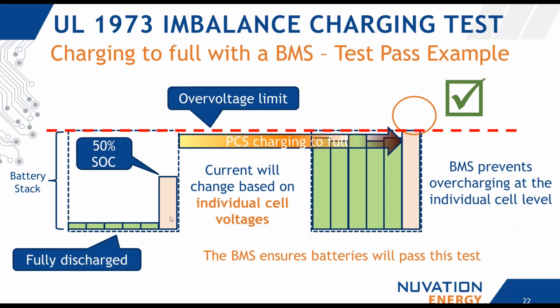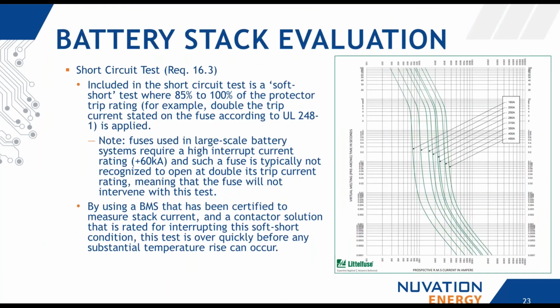And this safety, or the ability to detect individual cells and limit or disconnect the stack, is not necessarily a new concept to those in the lithium environment, where the individual cells being volatile and getting out of balance is just a fact of life that we're learning to deal with and manage safely. But a lot of these industries that have been around for a while are used to solving the problem in a different way. With UL 1973 coming out, it's now requiring a certain level of stack performance that just hasn't been seen before.